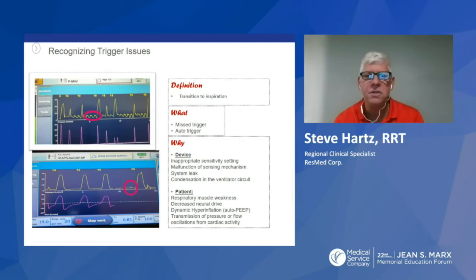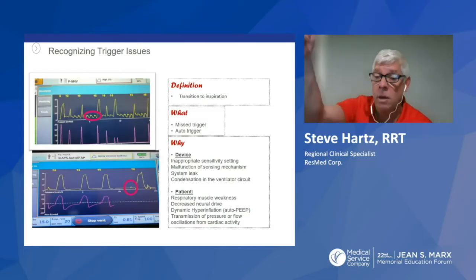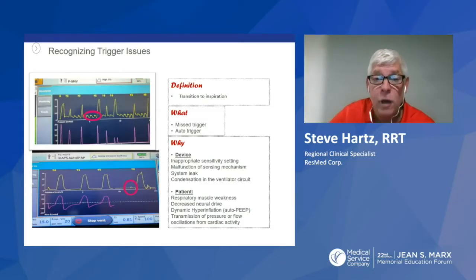The why, in some devices: there are devices that have sensitivity settings to trigger, and it might be inappropriate for that type of patient. It might be a neuromuscular patient. You might have a malfunctioning sensing mechanism. One thing I always look for in the beginning is usage leak, and then system leak. I don't know if you remember old CPAPs or ventilators back in the day, you had some slop in the tubing, and anytime you would see those auto-triggered breaths on your waveform, the patient may be complaining that something's going on, but you go in, empty the water trap, and that flow is now back in.